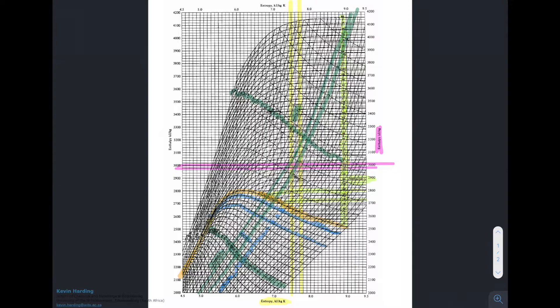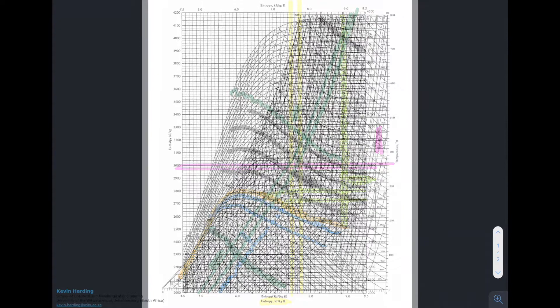In the middle of the diagram there is something called superheat. The superheat lines follow a pattern with values of 50, 100, 150, 200, mirroring the saturation line. This is not an absolute temperature — it is the temperature above the saturation temperature, and these lines follow all the way up to the top of the diagram.